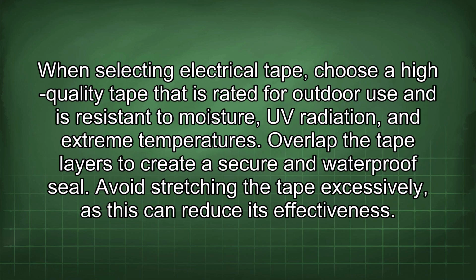When selecting electrical tape, choose a high-quality tape that is rated for outdoor use and is resistant to moisture, UV radiation, and extreme temperatures. Overlap the tape layers to create a secure and waterproof seal. Avoid stretching the tape excessively, as this can reduce its effectiveness.